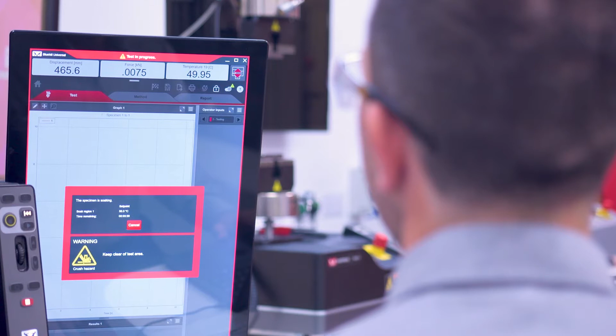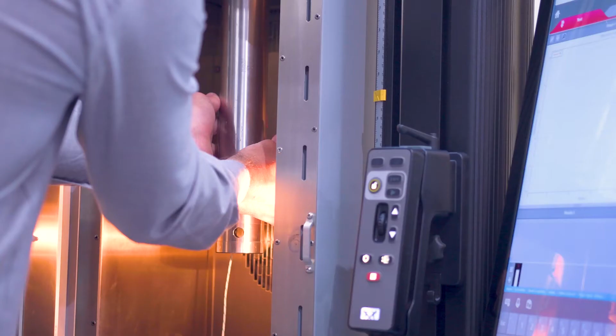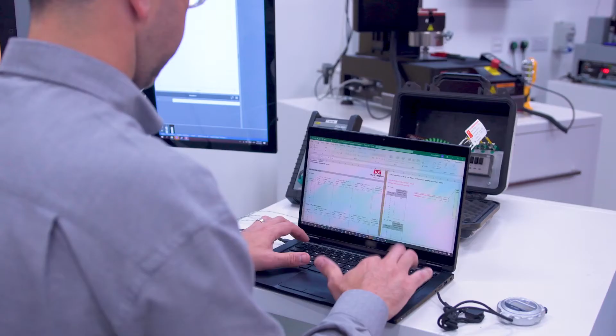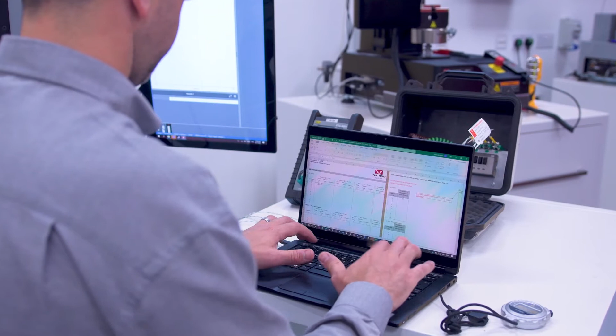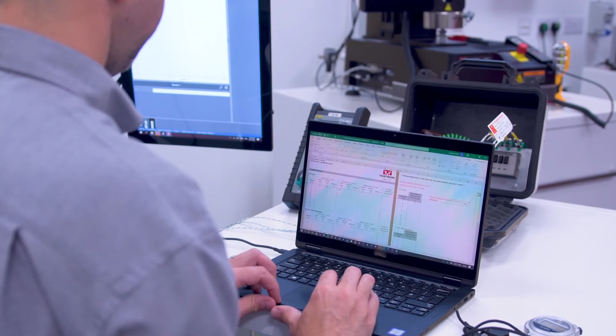To address this problem, Instron has developed a number of temperature calibration procedures that meet the most common requirements of laboratories and related manufacturing processes. These procedures are fully compliant with ISO and IEC 17025, and when performed, provide assurance that your test data is valid and your processes are properly controlled.